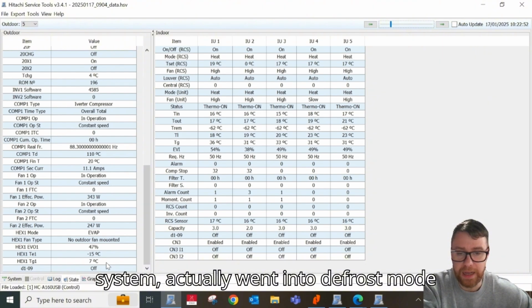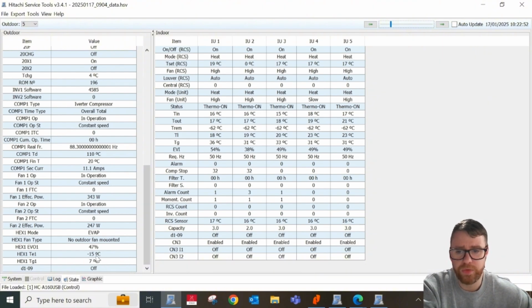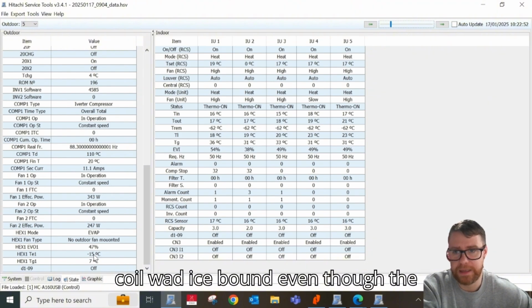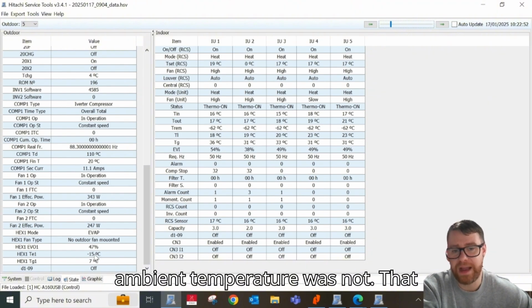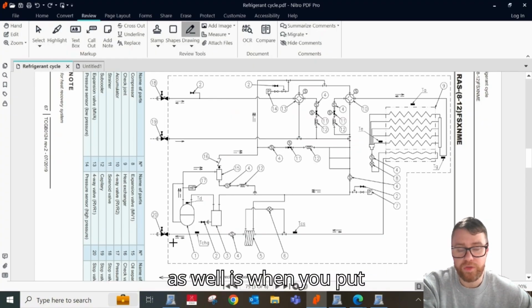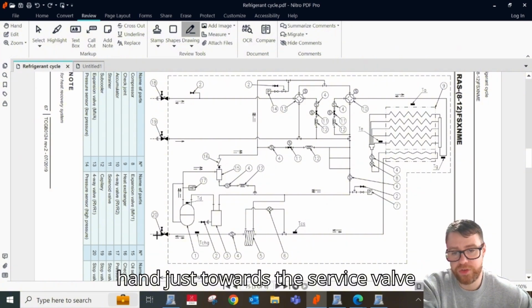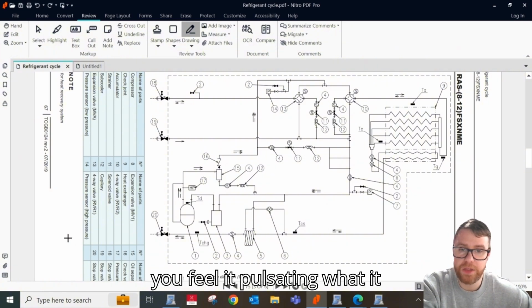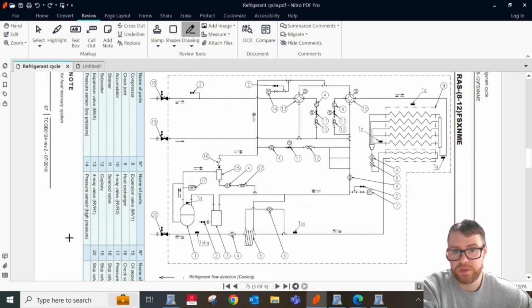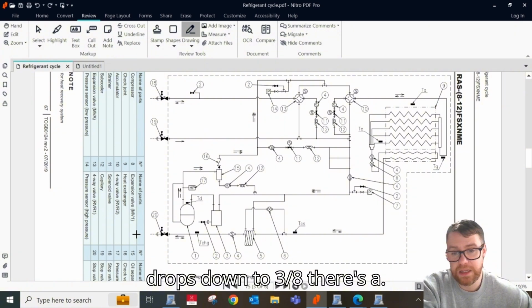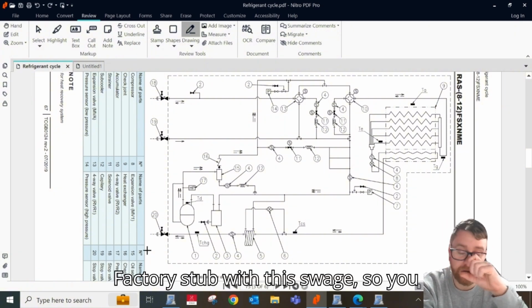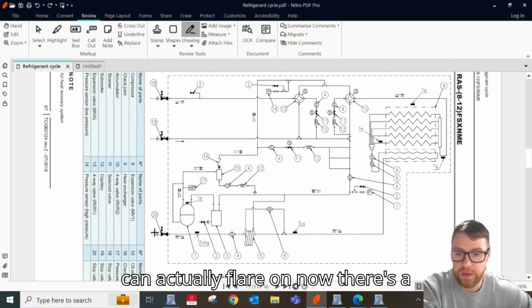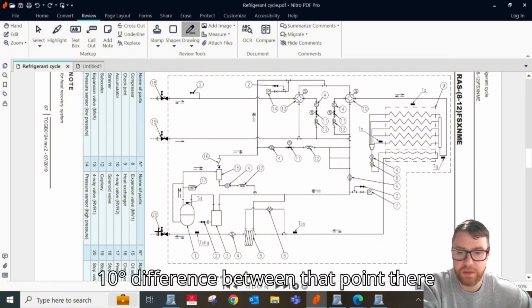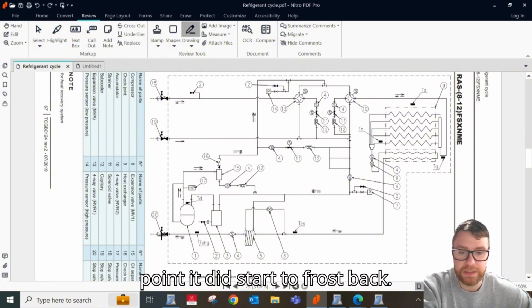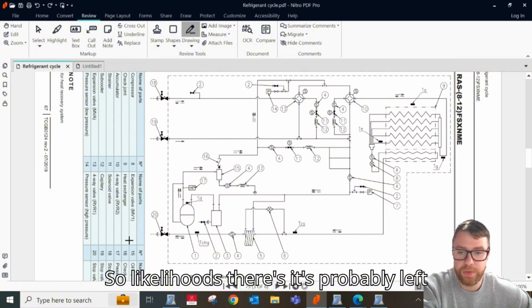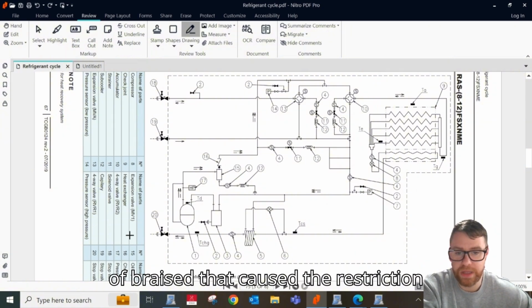And the system actually went into defrost mode because it could see that T1 was so low, it assumed that the outdoor coil was icebound, even though the ambient temperature was not that cold. But what you could feel as well is when you put your hand just towards the service valve, you actually feel it pulsating. And what it was, the half-inch liquid that drops down to 3/8. There's a factory stub with a swage, so all you need to do is braze onto it and then connect your flare on. Now, there was a 10-degree difference between that point there and the pipework coming in, and at one point it did start to frost back. So likelihood it's probably left the cap in on the pipework as it was brazed, and that's caused a restriction.